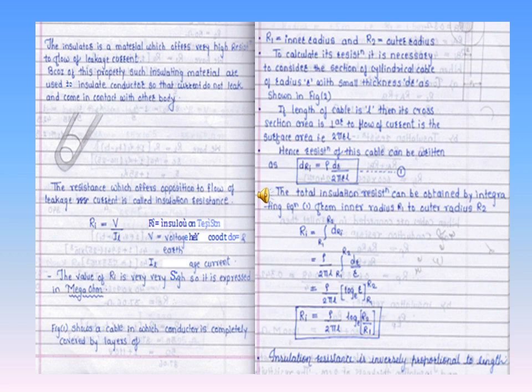Insulation resistance is the resistance offered by the insulating material to the flow of leakage current through it. We denote it as Ri = V / IL, where V is the voltage between the conductor and earth, and IL is the leakage current. The practical value of Ri is very high, lying in the range of mega ohms. Typical insulators are air, glass, mica, porcelain, rubber, oil, and varnish.